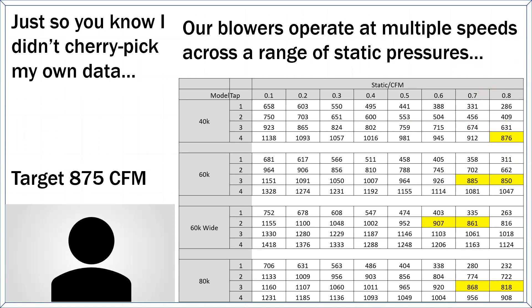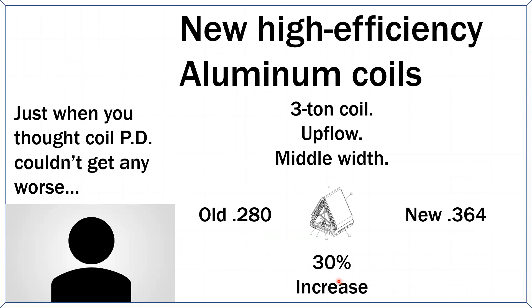As we improve our efficiency, right? The pitfalls of Manual S. How about the new coils we're using? Anybody ever looked up the pressure loss numbers on them? I did. So the old coil that we were using as the standard for high efficiency, I'm not talking 20 years old, I'm talking last year, right? The old coil from last year, at a 3-ton at 1200 CFM, had a pressure drop of 0.28 when it was wet. The new equivalent coil that's going to work with SEER2, 0.36. That's a 30% increase in restriction. Not good. Unintended consequences, man.